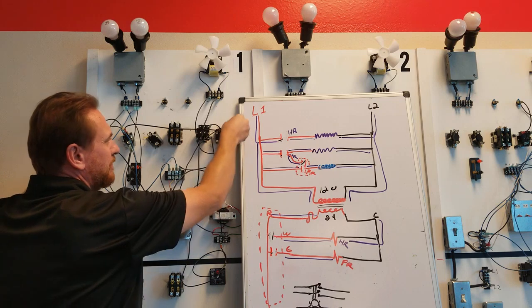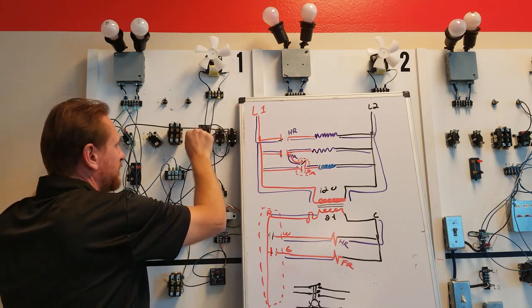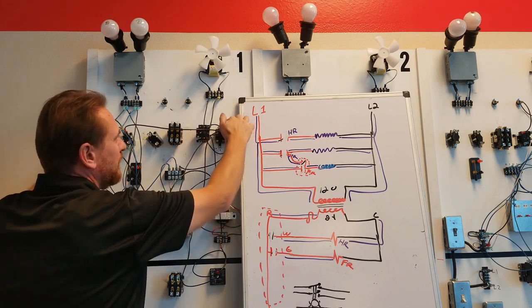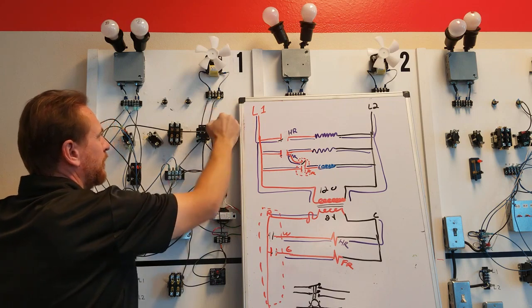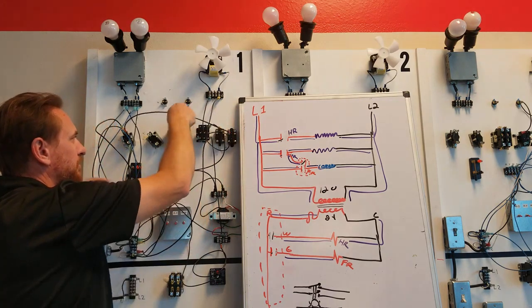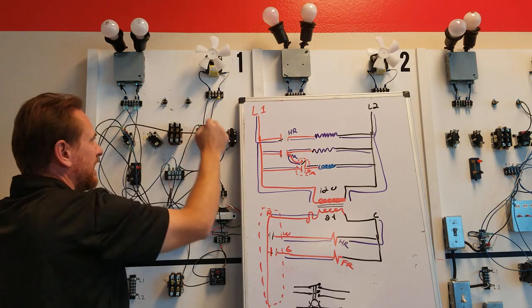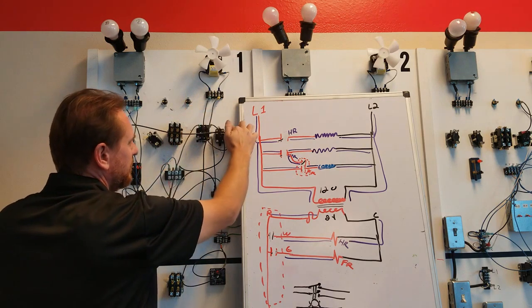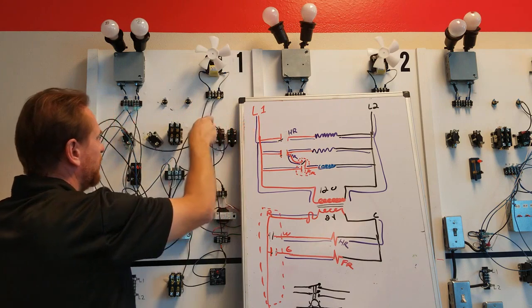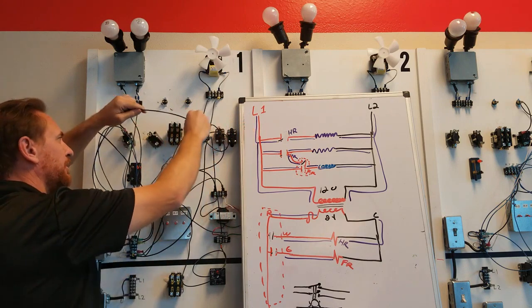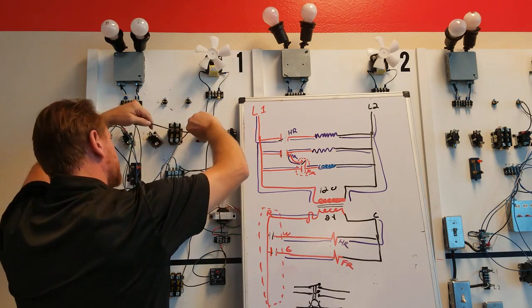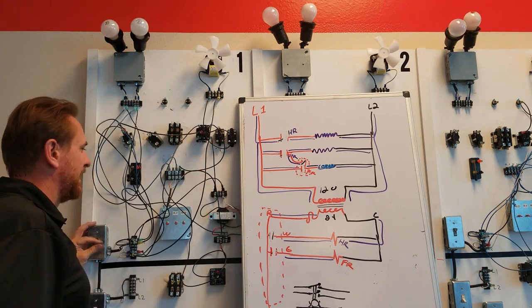This is the common side of my relay, so we'll put that on the common side here that's always being used. Normally open was at the top. Number 3 on this relay shows normally open, so we'll put it here. And then normally closed between 1 and 2. So on this one, this is our normally closed wire from our heater. We're going to put it on terminal number 2. So let's see how it works differently.